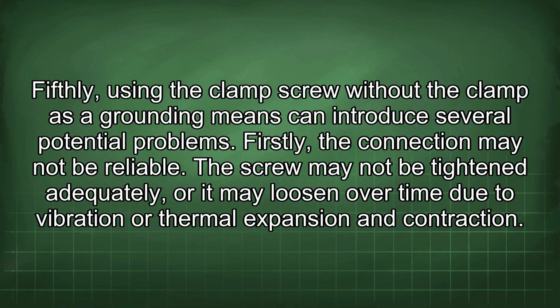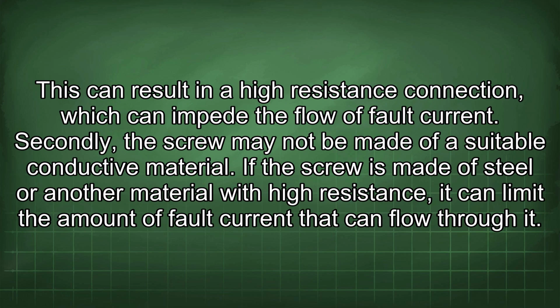Fifthly, using the clamp screw without the clamp as a grounding means can introduce several potential problems. Firstly, the connection may not be reliable. The screw may not be tightened adequately, or it may loosen over time due to vibration or thermal expansion and contraction. This can result in a high resistance connection, which can impede the flow of fault current.